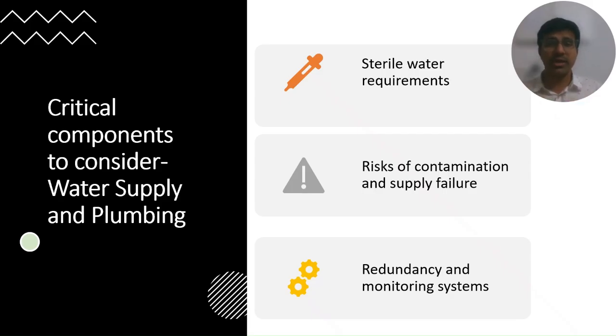The water is being used for irrigation, rinsing instruments, sometimes even wound care in the OT. Contaminated water can introduce pathogens directly into the surgical field. Biofilm formation can also happen in the pipes if not frequently checked. So redundant pumps, dual water lines, and real-time pressure monitoring systems are essential. Water is usually taken for granted in the OT, but when it fails, everything else can fail. So make plumbing also part of your safety conversation.